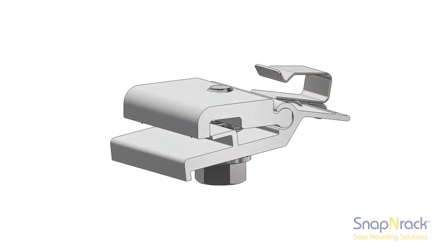The SnapNrack MLPE attachment kit is designed to attach an optimizer to the module frame using a standard half-inch socket. Two bonding pins electrically bond the chassis of the optimizer to the module frame. The MLPE attachment kit comes pre-assembled with a smart clip 2 to help manage conductors.